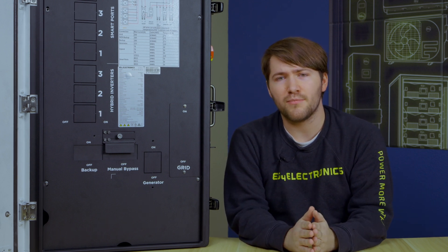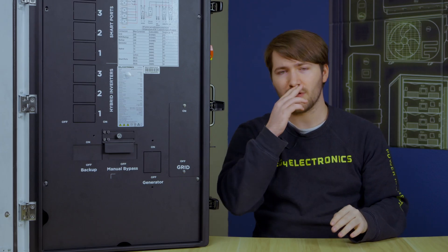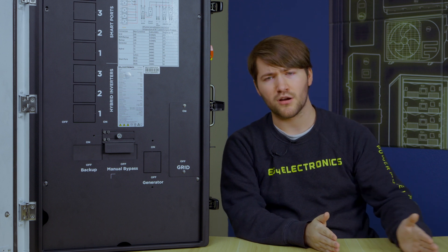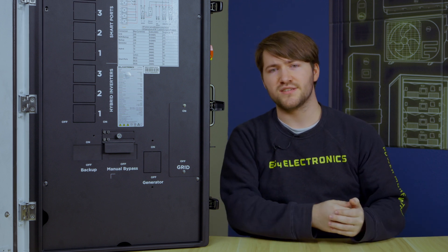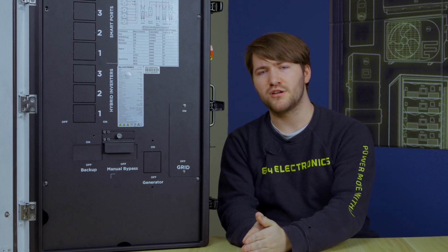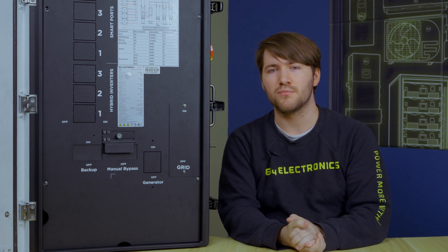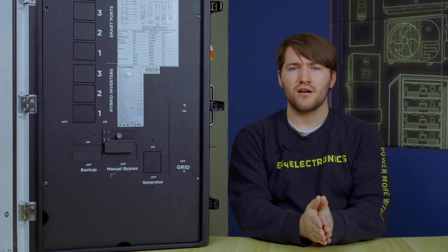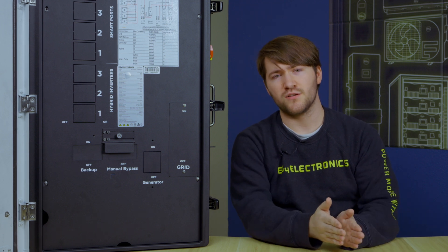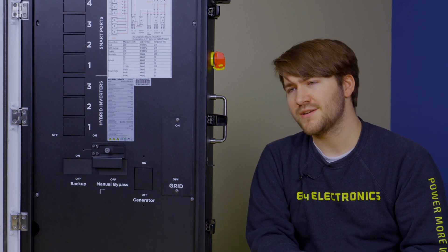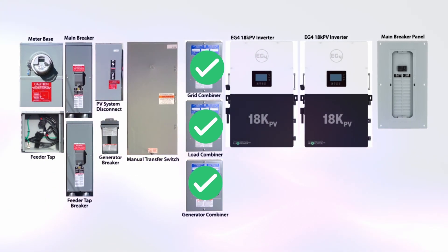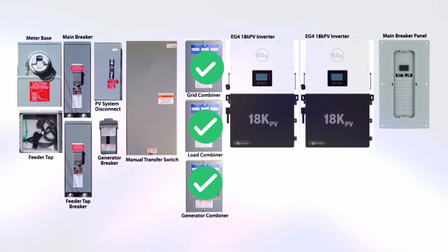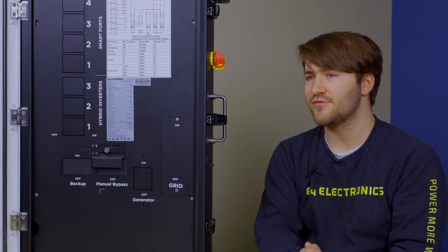We have a grid combiner panel and an inverter output combiner panel. Now the grid and generator are more like splitters as you have your utility power run into this utility combiner panel. Then it splits to each of the inverters in the system, in this case two, which then goes through your inverters to your output combiner panel, which recombines the power between the two systems. And then that runs to your loads. Now the generator combiner panel simply splits that generator power into each of your inverters, which again gets combined through the inverter output combiner and run to your loads. The grid boss has all of these features included into it. You're effectively putting all of those combiners into one single bus. And that bus again is controlled through software to be able to manage all of these different paths effectively and safely.